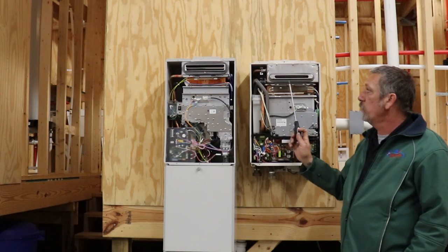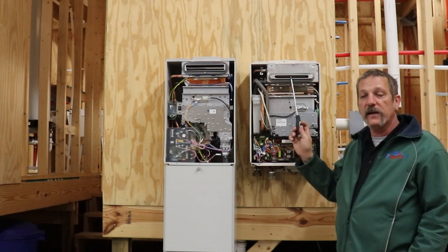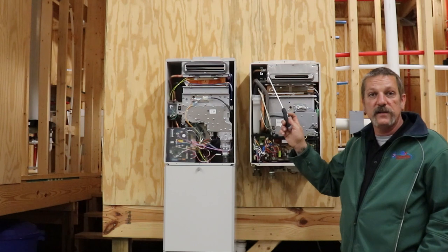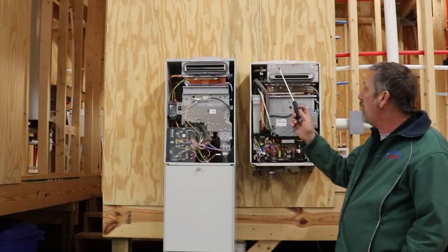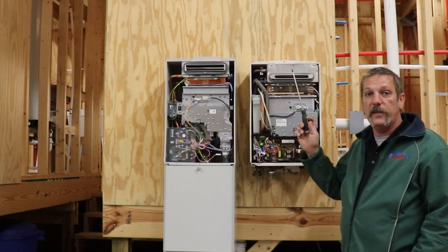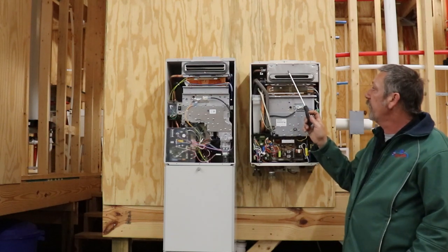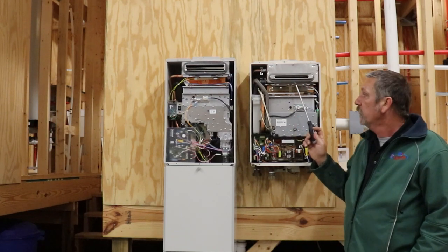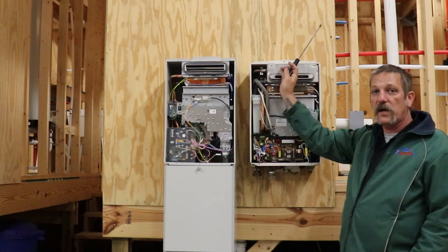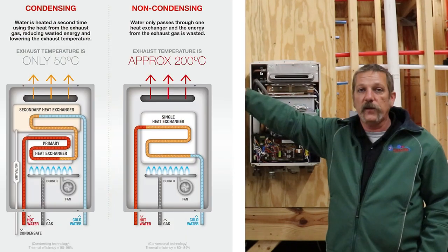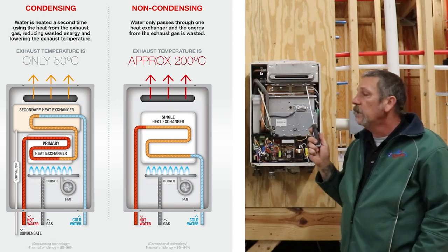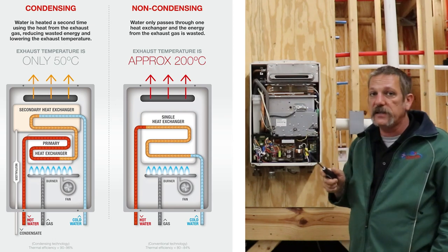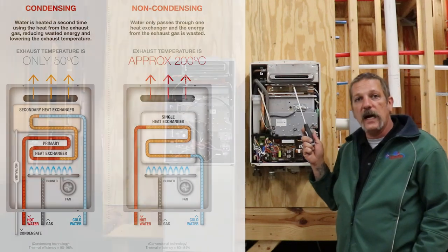And it's gonna be burning the moisture off, but when it gets up to here, that is gonna be 65 degree water, cold water coming in from under your house or whatever, out of the road, or it could be a well. And so that's cold water coming into that exhaust. This exhaust is gonna be a lot cooler than this exhaust. But what happens when you preheat that water, yes, it's energy efficient, yes, it's great, but you create condensate.